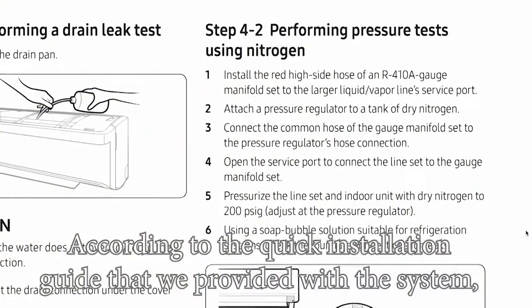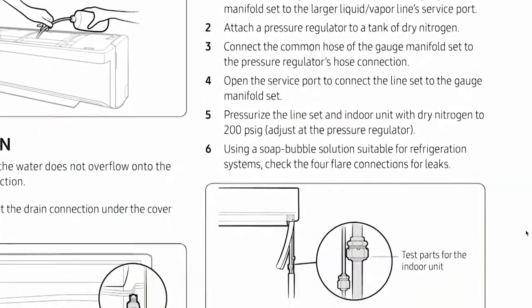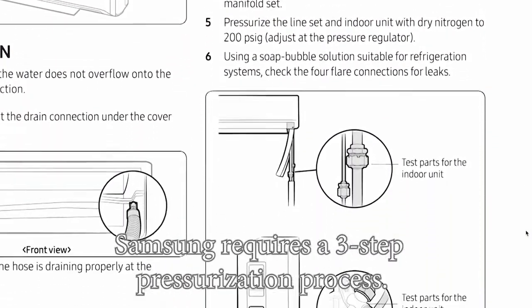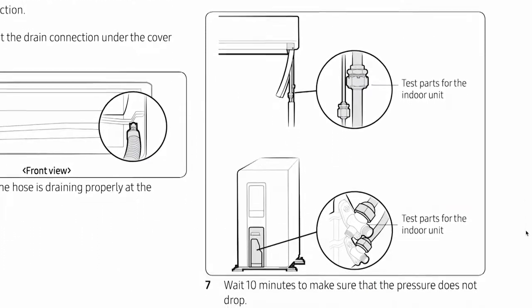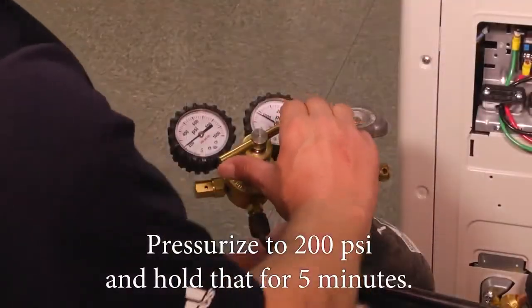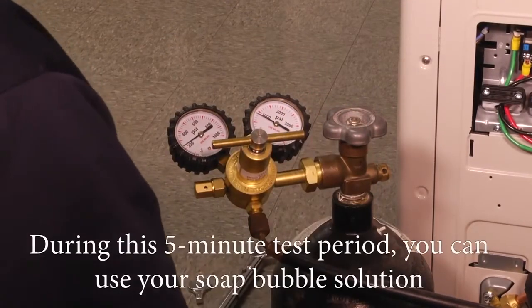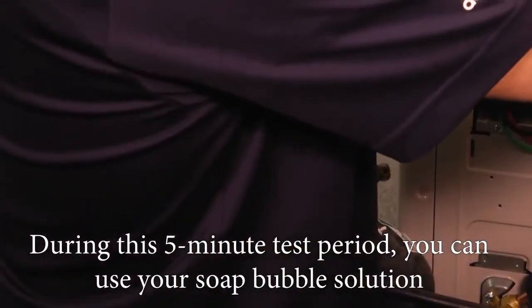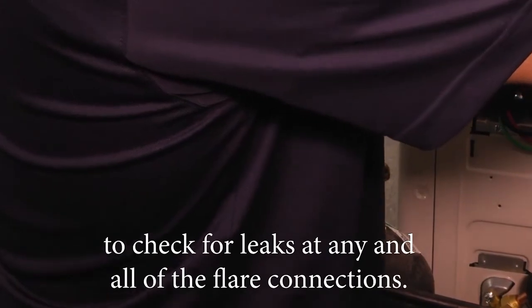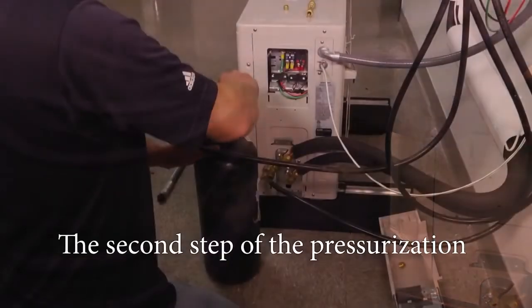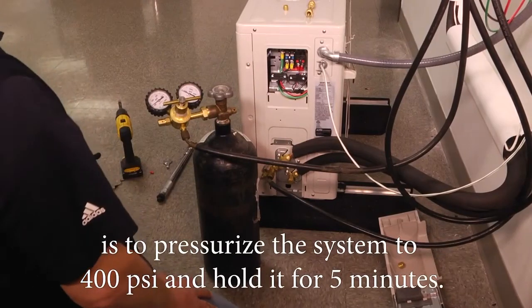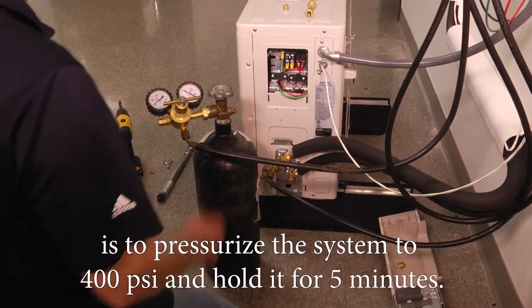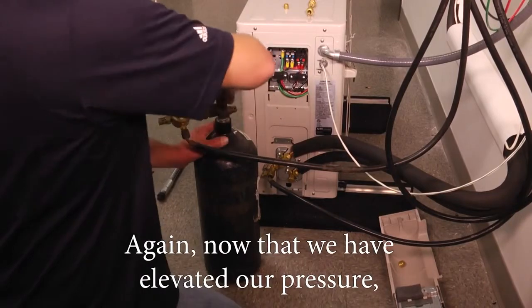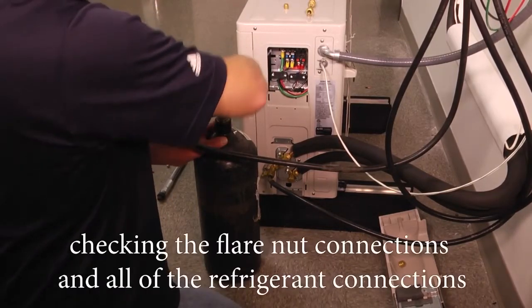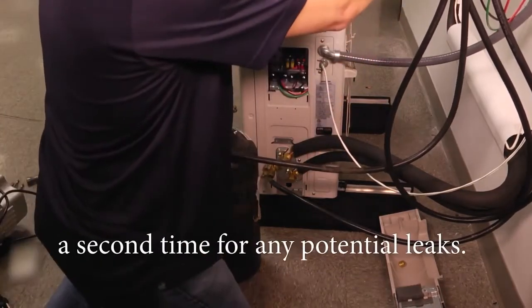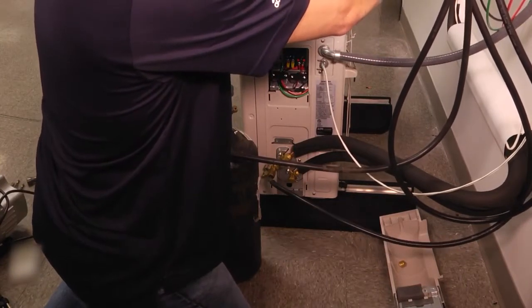Now, according to the quick installation guide that we're provided with the system, Samsung requires a 3-step pressurization process. Pressurize to 200 psi and hold that for 5 minutes. During this 5-minute test period, you can use your soap bubble solution to check for leaks at any and all of the flare connections. The second step of the pressurization is to pressurize the system to 400 psi and hold it for 5 minutes. Again, now that we've elevated our pressure, checking the flare nut connections and all the refrigerant connections a second time for any potential leaks.